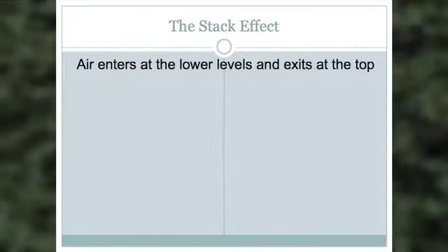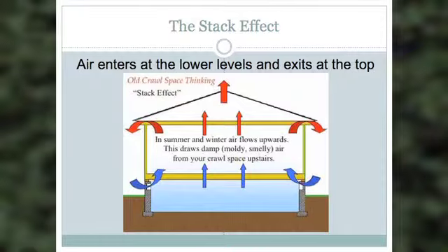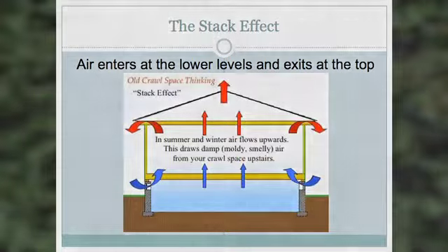What's the fourth way? It's called air leakage. And that air leakage happens primarily by this phenomenon called stack effect. Stack effect is the tendency for a building to draw cool air in at the bottom and let hot air out at the top. So when we're looking for air leaks, where's the most important place for us to start looking? We want to look for leaks at the ceiling line. When we get into thermal envelope, we'll get into more details on that.